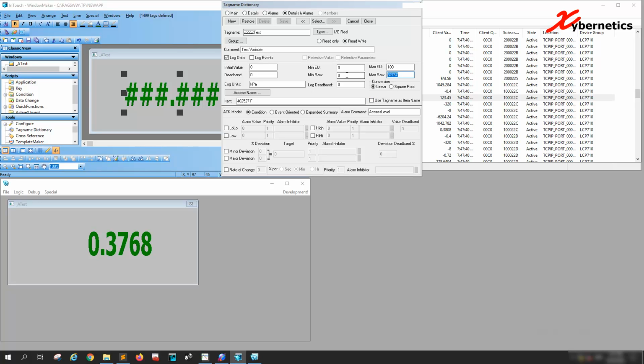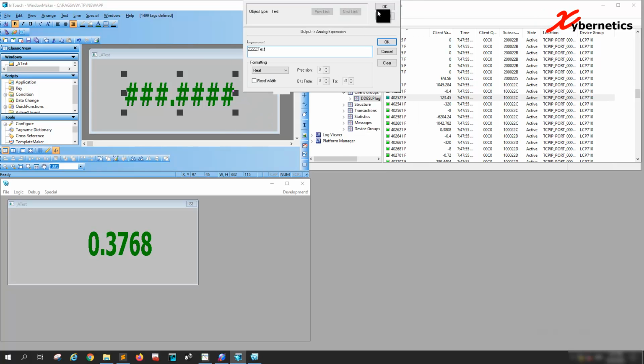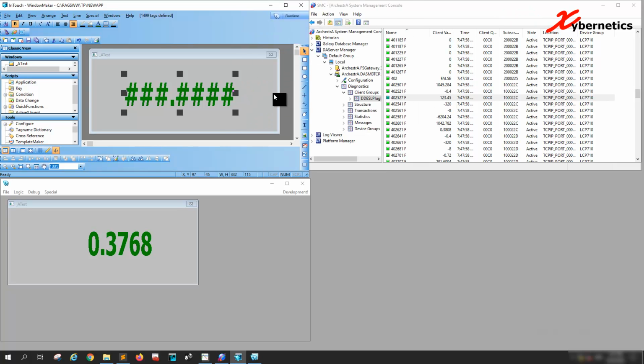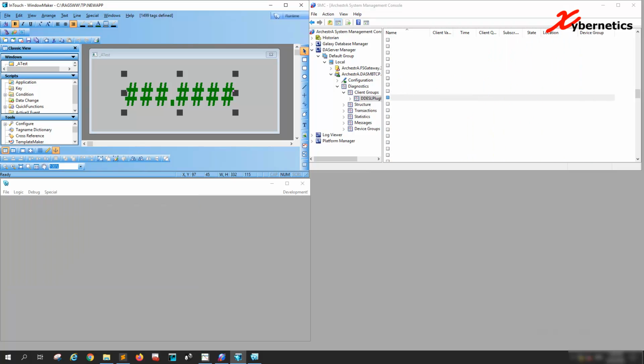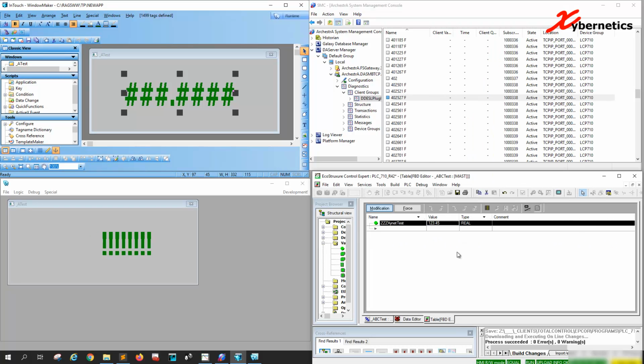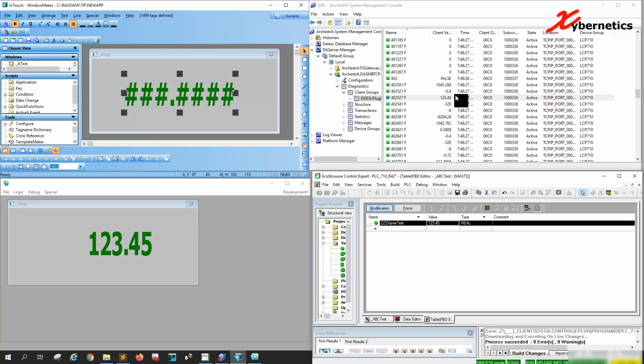What you have to do is to copy, and then you gotta make it exactly the same. If you do that, it will assume that no scaling is required, or rather they are equal word for word, and they will show you whatever is necessary. I guess whatever this thing value is being shown here. I'm gonna save it. File, save. And you can see that this matches once the polling is done. You can see that the programming environment matches the SMC Modbus TCP driver, and that matches as well.